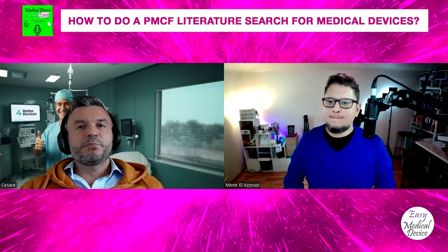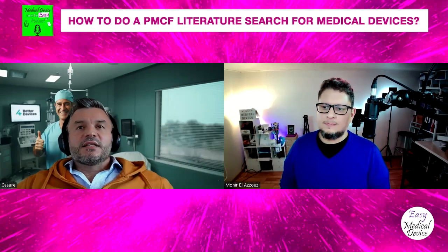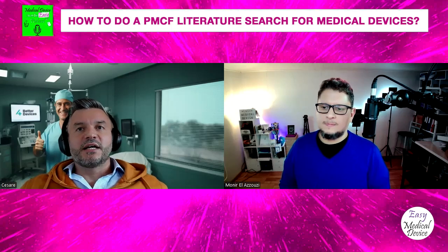No, it's completely different from the searches for state of the art, because the goal is that you're not trying to find the cream of the evidence. You're trying to find anything. So you try to be as broad as possible. In theory, you try to use the query that is as broad as humanly possible. Obviously, if you have a device that's called S2 and you type S2 in Scholar or PubMed, you are going to get hundreds of thousands of results, because S2 can be the name of your device, like 20,000 other things. But maybe then you could add the name of the manufacturer, or you could add some specific keyword that would tend to isolate the specific device.